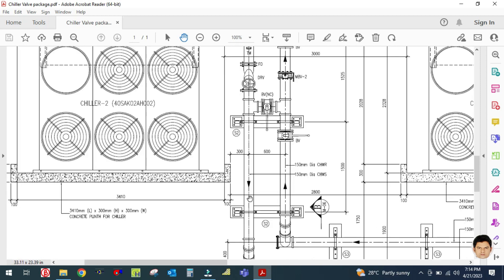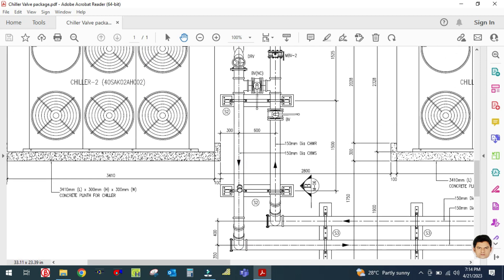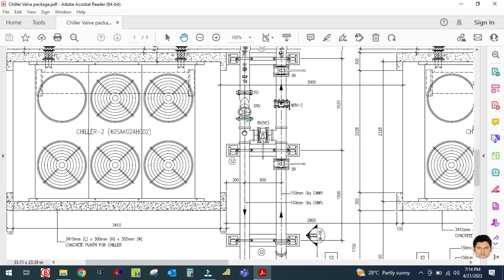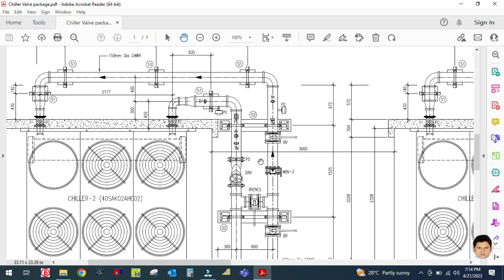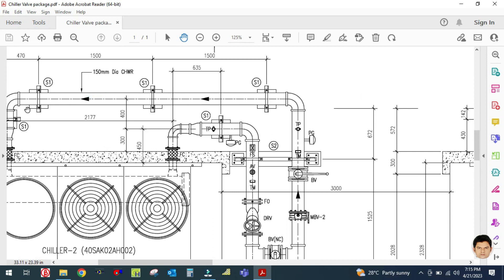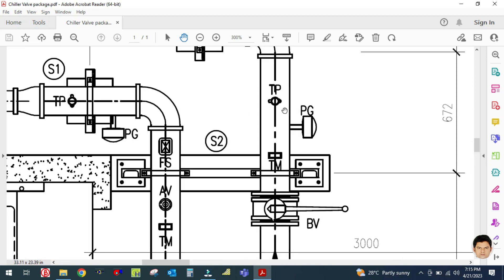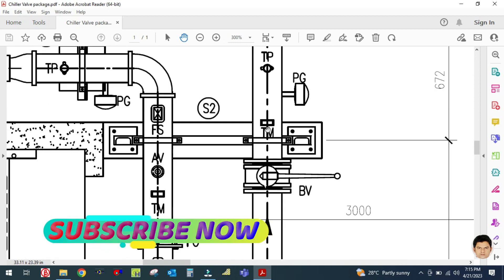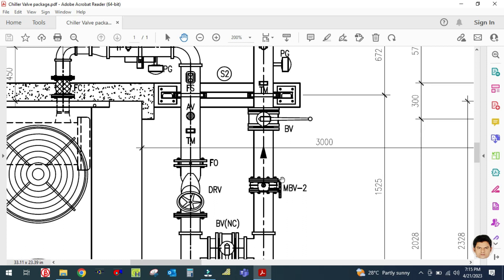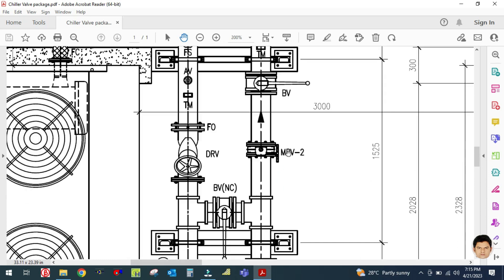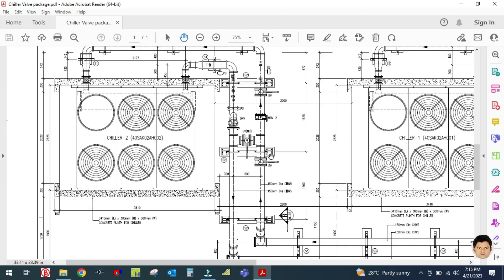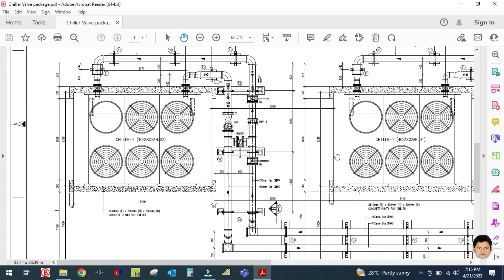After the double regulating valve there will be an isolation valve on the discharge line. On the suction line you can see there will be a flexible connector, then a pressure gauge and temperature gauge — TM is nothing but the thermometer or temperature gauge. Next is a butterfly valve used as an isolation valve, and then MBV, which is the motorized valve.